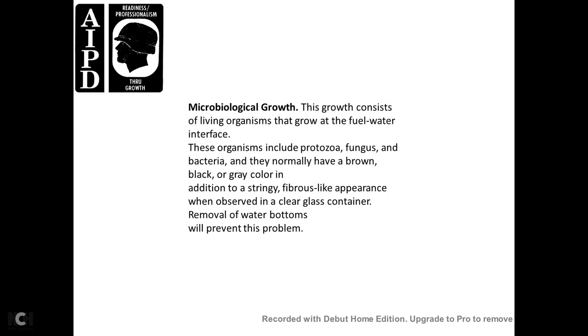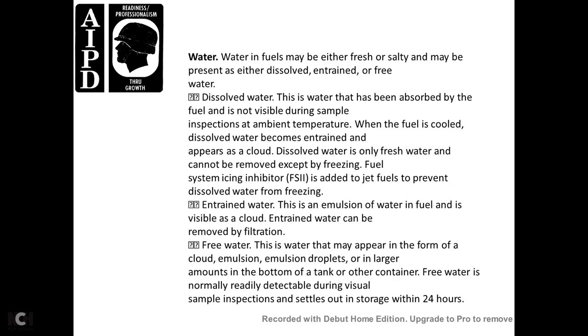Microbiological growth consists of living organisms at the fuel-water interface, including protozoa, fungus, and bacteria, normally brown, black, or gray in color with a stringy fibrous-like appearance visible in clear glass containers. Removing water bottoms will prevent this problem. Water in fuel may be fresh or salty, and may be present as dissolved, entrained, or free water. Dissolved water has been absorbed by the fuel and is not visible during sample inspection at ambient temperature.